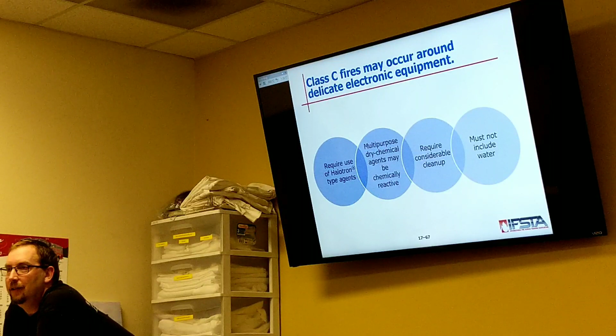Water's inappropriate in those because of what? Conductive - it's conductive, a bad conductor, but it's conductive. Anybody know what the voltage line is, the minimum voltage for it to be conductive? If you have this, 50 volts - 40, according to the book it's 40. OSHA says 50, NFPA says it's 40. Let them argue about it, they argue about everything else anyway. All I know is I'm legally required to lock something out if it's 50 volts or above.